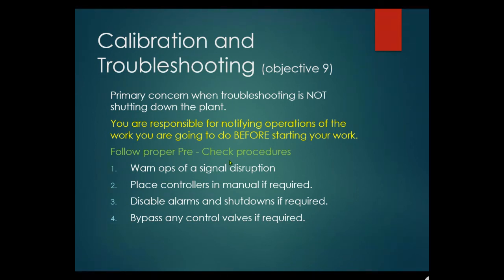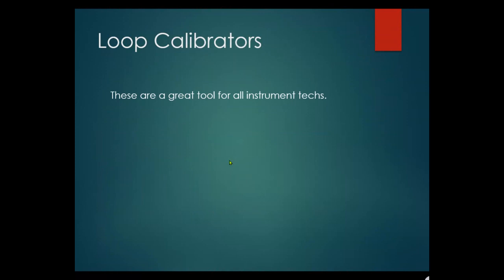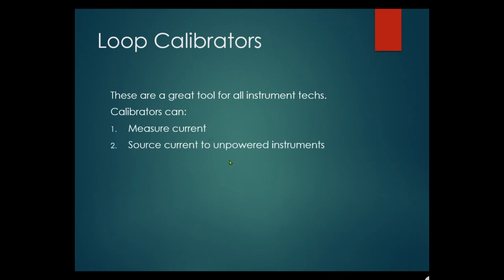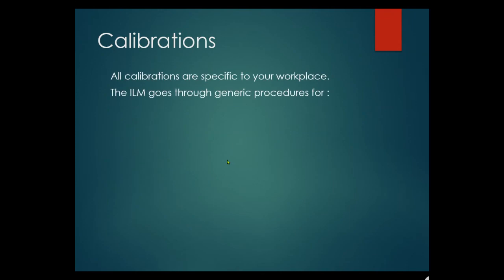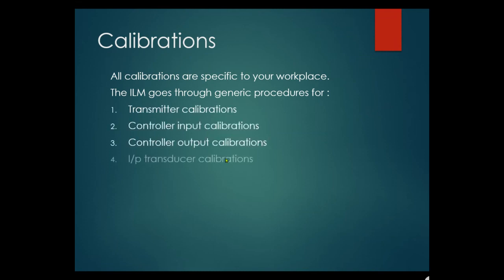Calibrations in the shop are best, but you still have to break the loop to install a new transmitter. Loop calibrators are great tools for instrument techs — you can measure current, source current to unpowered instruments using tools like the 724, 375, or Trek calibrators. Fluke meters also offer options. All calibrations are specific to your workplace. The ILMs cover transmitter calibrations, control input calibrations, controller output calibrations — trims, zeros, I/P transducer calibrations.